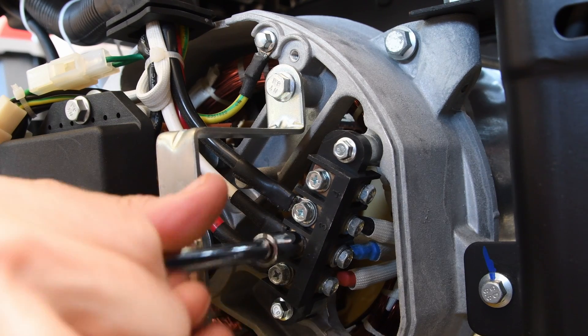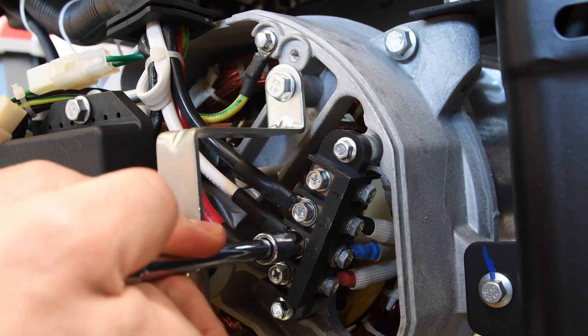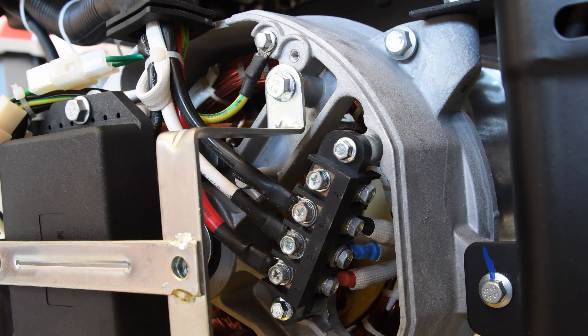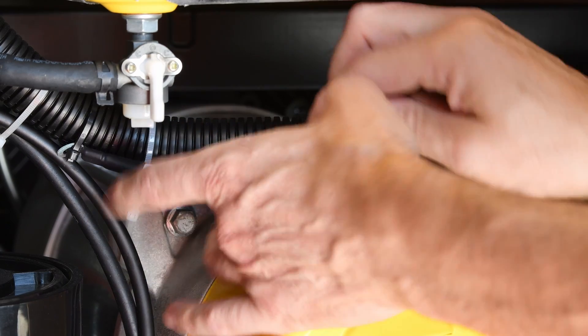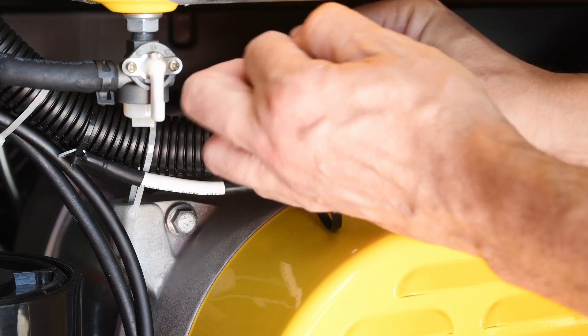Put the bolt back on. And now this generator is floating neutral. And in order not to lose this cable, I'm going to attach it with a zip tie over here. So in case I need it in the future, it's going to be available.